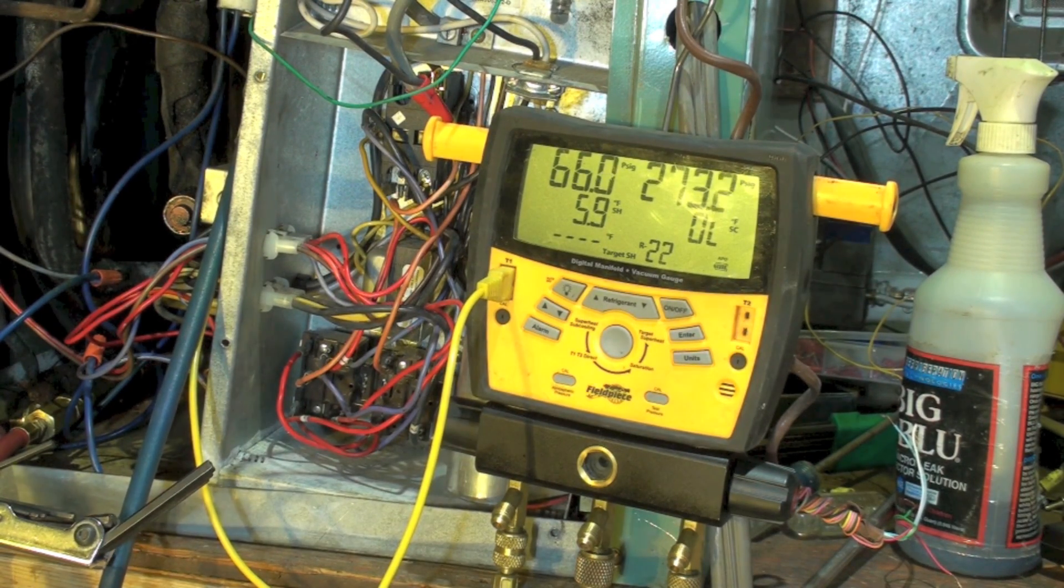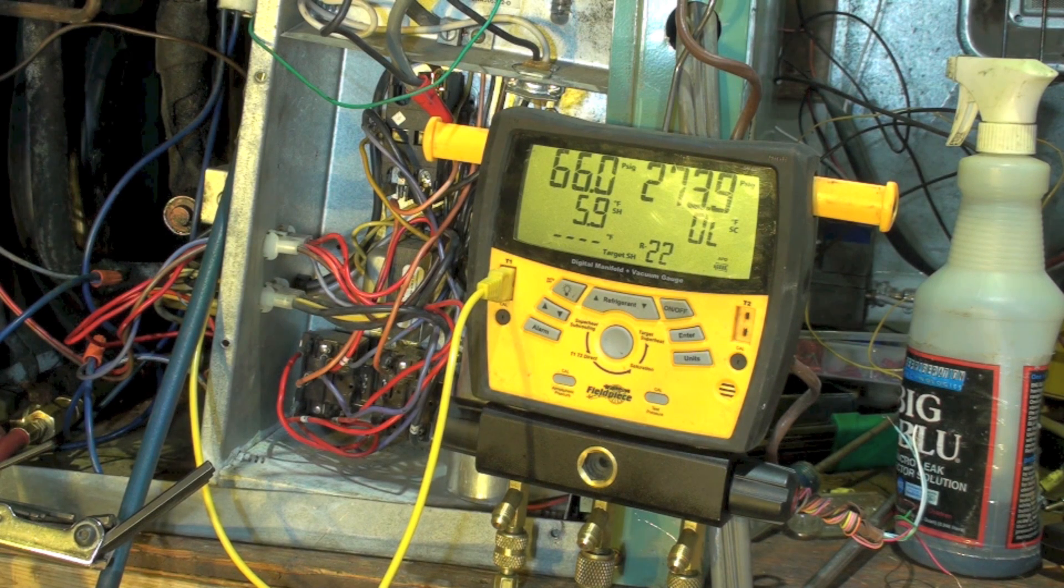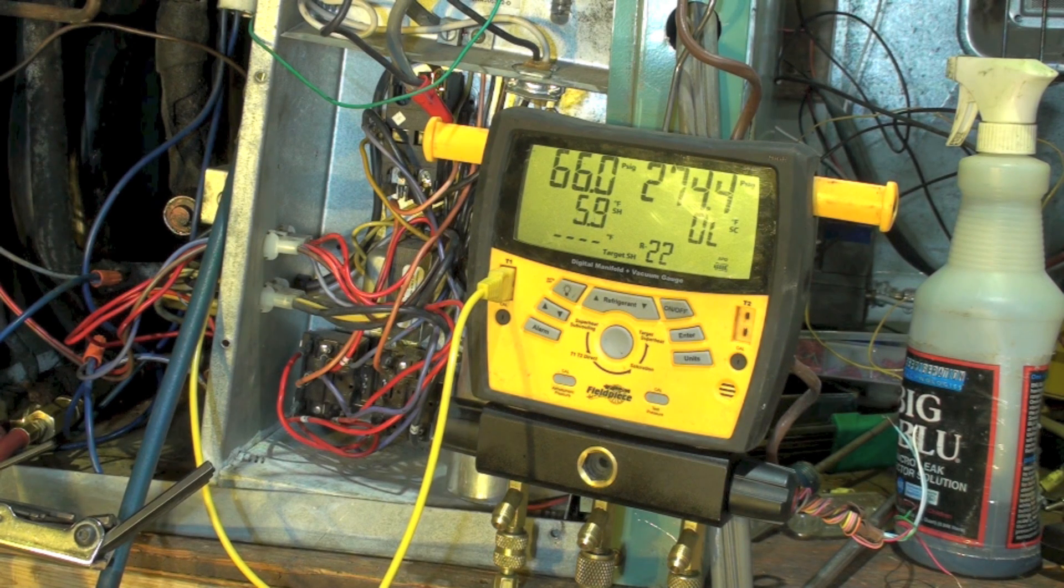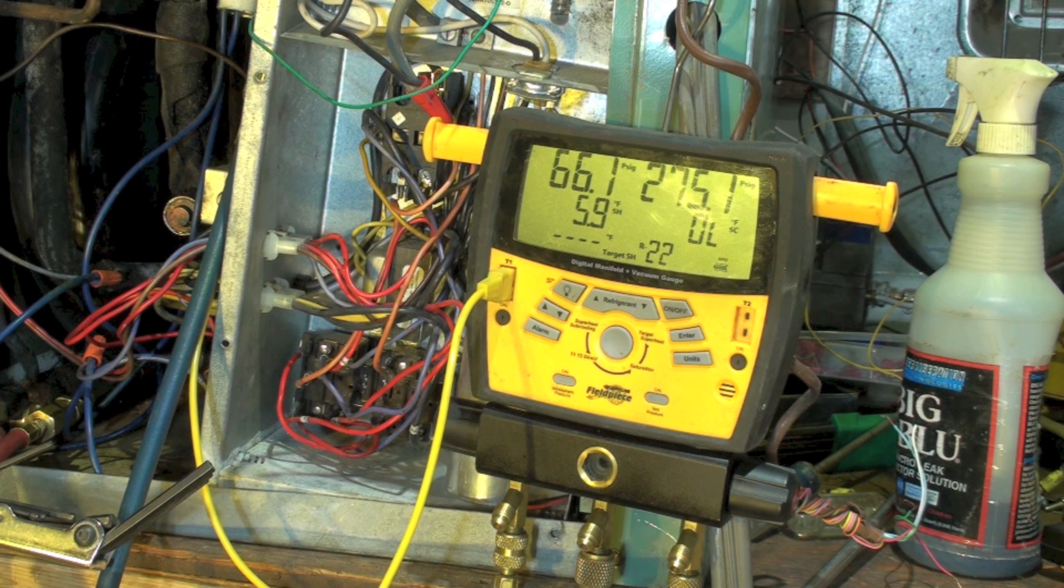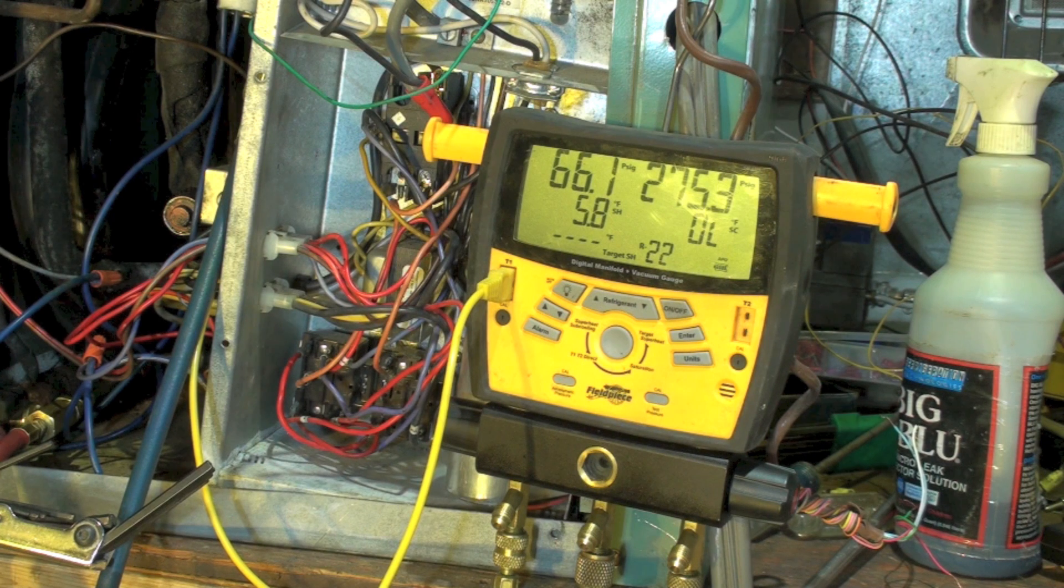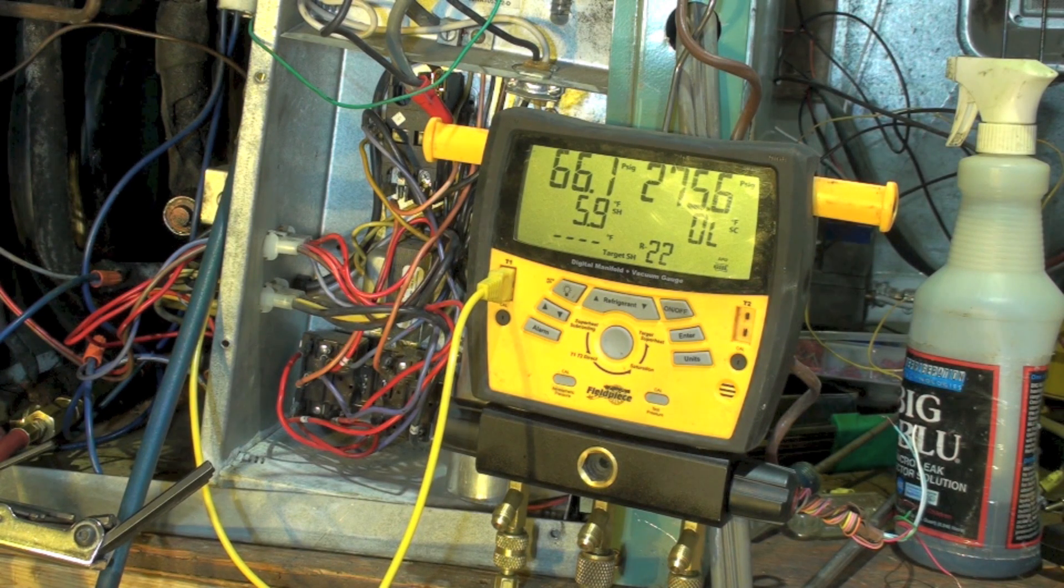Okay, what we're looking at here is a water-cooled or water source heat pump. It's in cooling mode, so it's acting like a water-cooled condenser. We're using water to condense the refrigerant. Right now our head pressure is 275, suction pressure 66, return air temperature is about 78, and we got about 17 degrees across the coil.